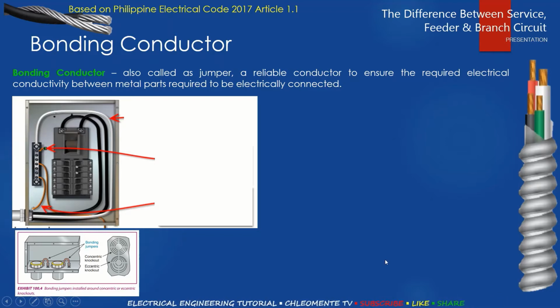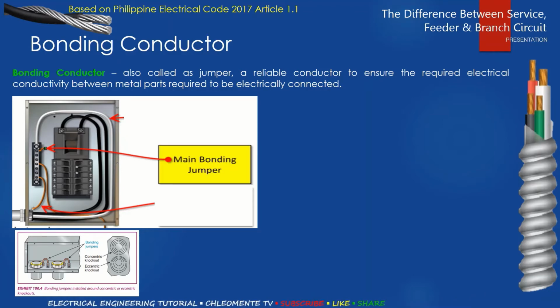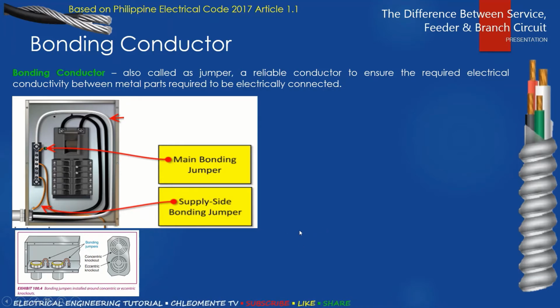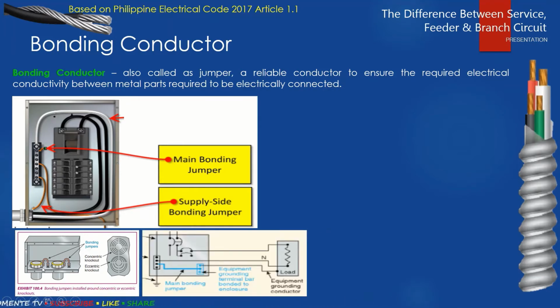So, sabi ng PEC, ang bonding conductor is a reliable conductor to ensure the required electrical conductivity between metal parts required to be electrically connected. So, siya yung conductor na kinokonekta natin sa mga metal parts ng ating mga electrical equipment. So, sa ating panel, meron tayong tinatawag na main bonding jumper at meron tinatawag na supply side bonding jumper. So, sa mga pipes natin, meron din yung sa mga knockout. So, meron diyang mga nilagay tayong bonding jumper to connect yung metal between metal parts, no?